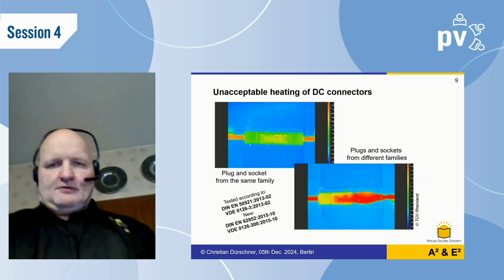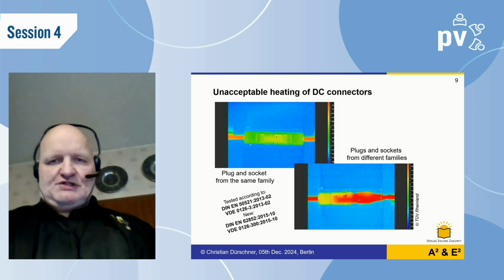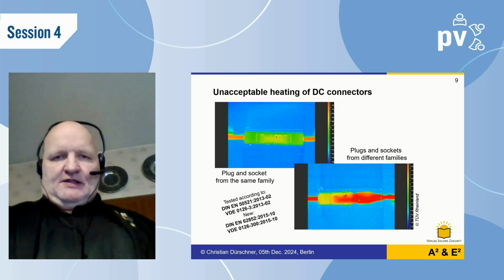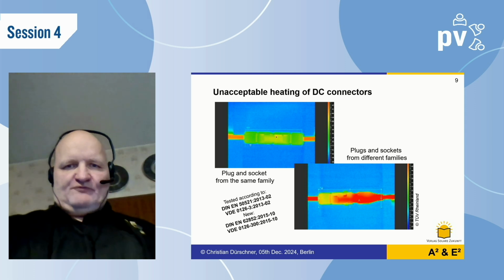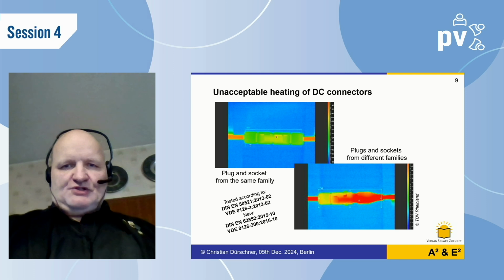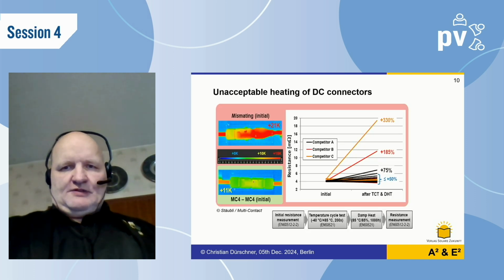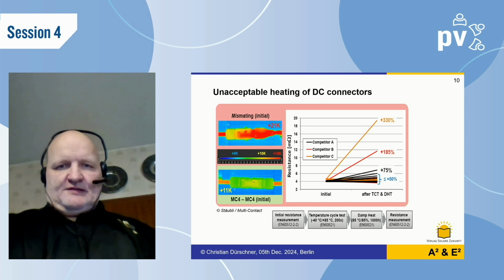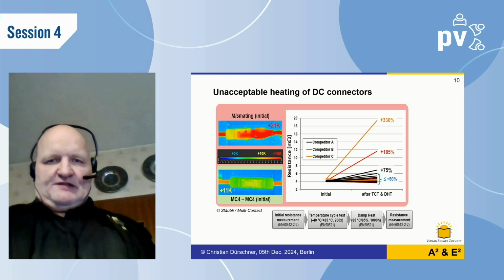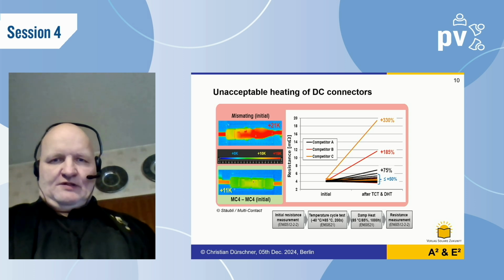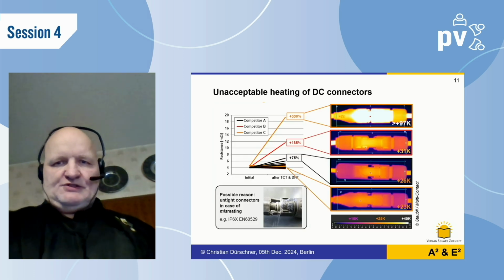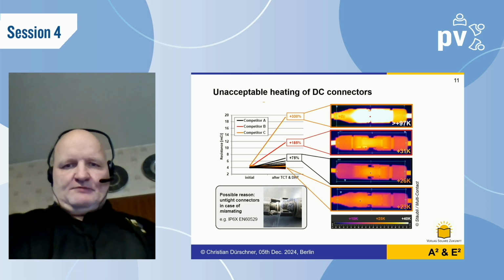What can go wrong is that the connection in the connector is bad. The left picture shows everything fine, just a little warming. The right picture shows it's not so good. What can go really wrong is when you start with a slight warming of about 10 or 20 Kelvin for the wrong connection, but it will increase up to 100 degrees Celsius. At least it might burn. I have brought you some pictures to show that.